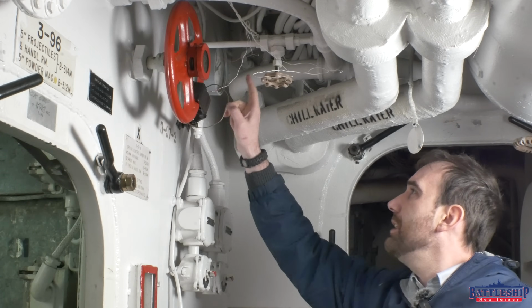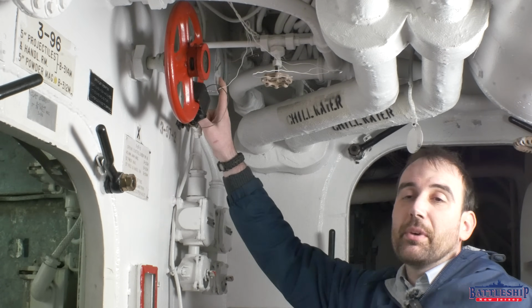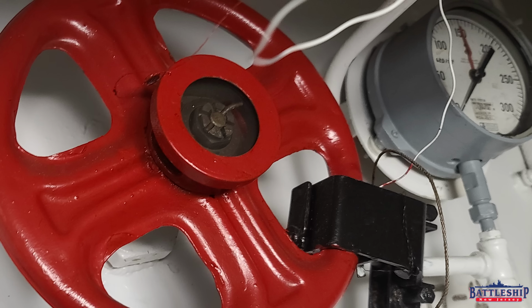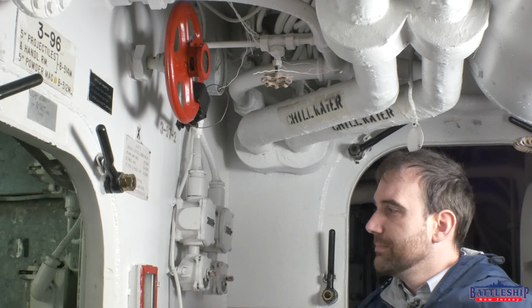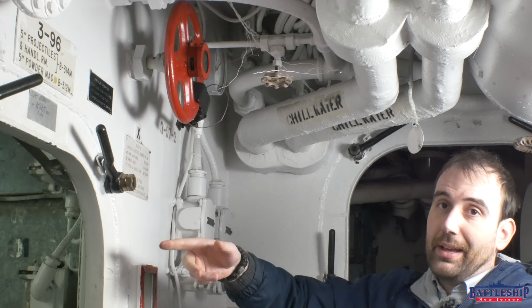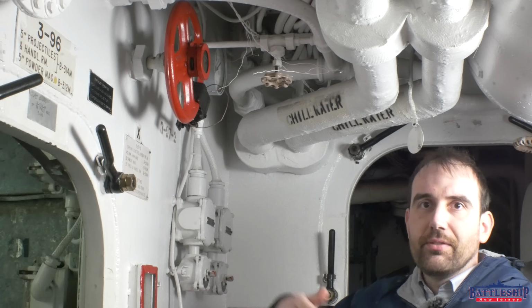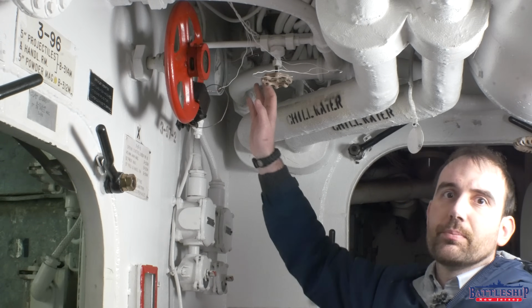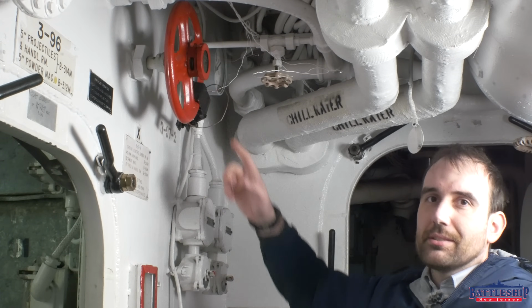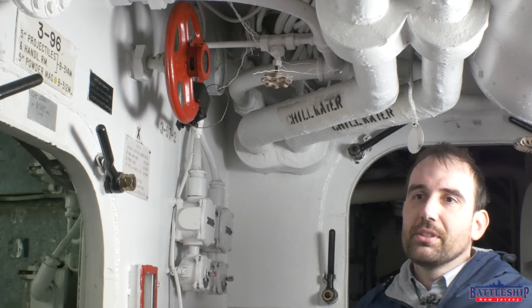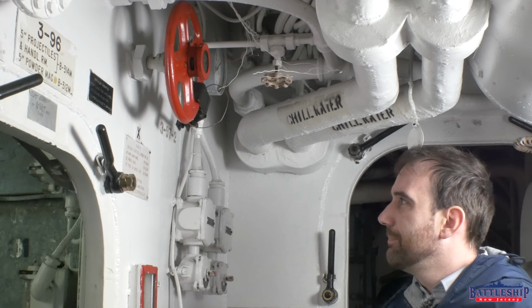There's even a gauge here showing how much pressure the fire and flushing main has right now. Obviously if there's no pressure, you can open that valve all day and it won't flood the space. When you start flooding the space and it draws on all your firefighting water for an hour, you'll probably lose pressure on that pump, so you'd need to turn on another firefighting pump to keep the rest of the line charged.